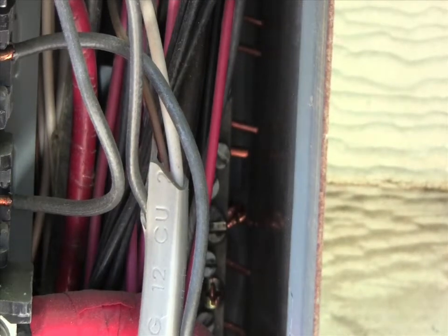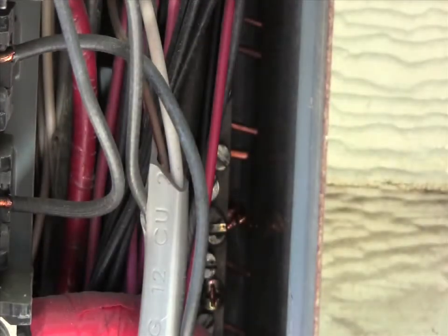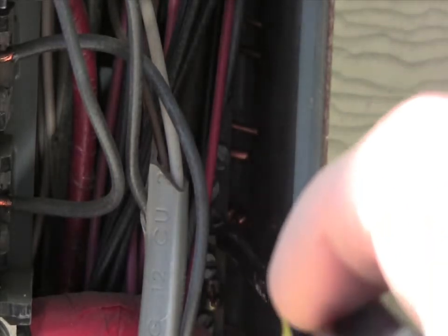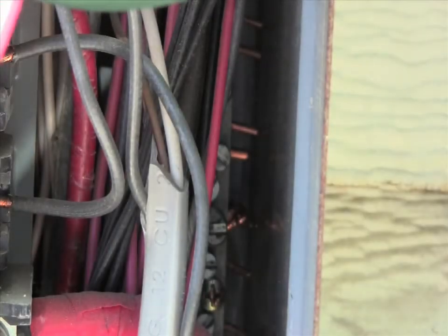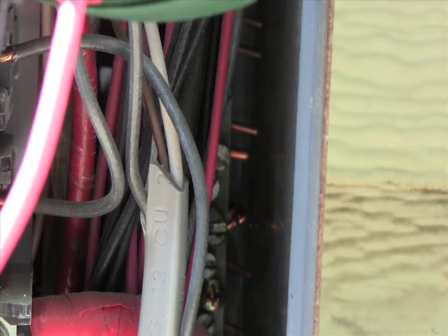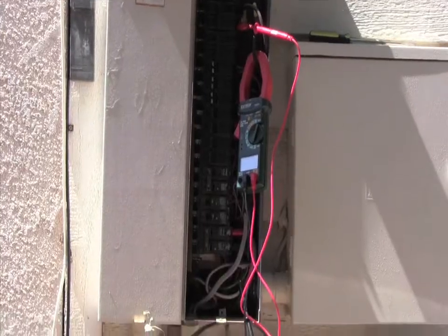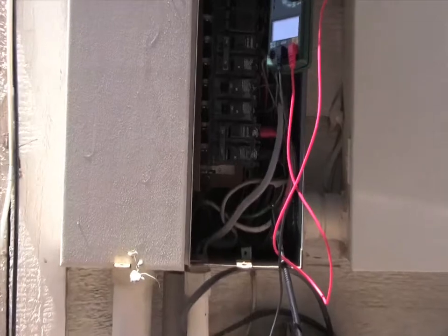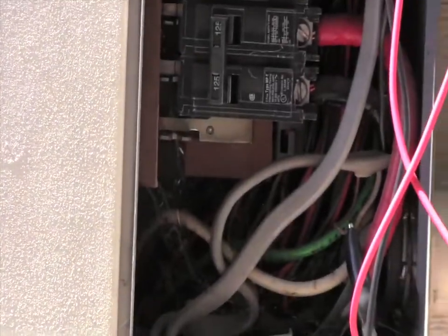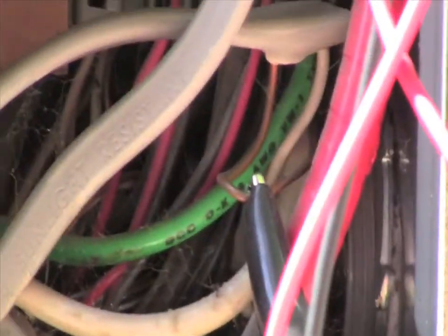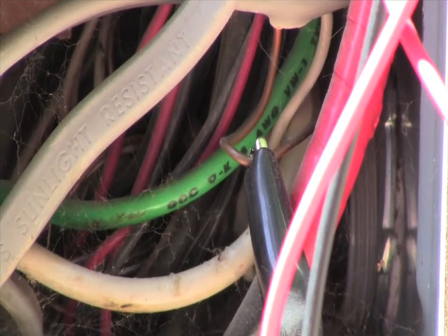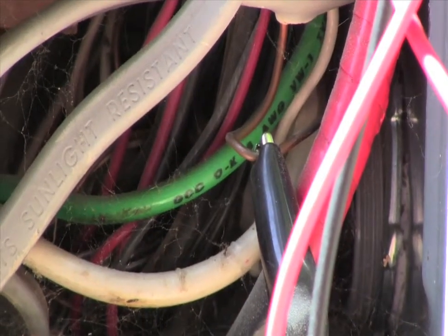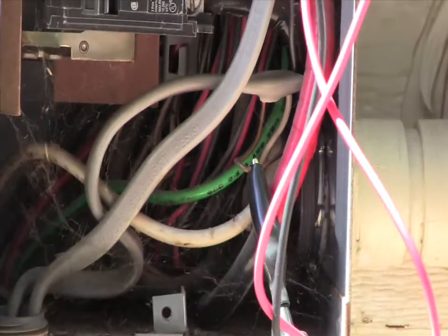So if you're looking here, this is where the ground bar is down inside here, like so. So we're going to clip on our black lead onto the ground. I couldn't get a good finger hold on the ground bar at the bottom, so if you notice right here, there was a ground wire out loose where I could clip onto it, and that's legal as long as you can ground it.